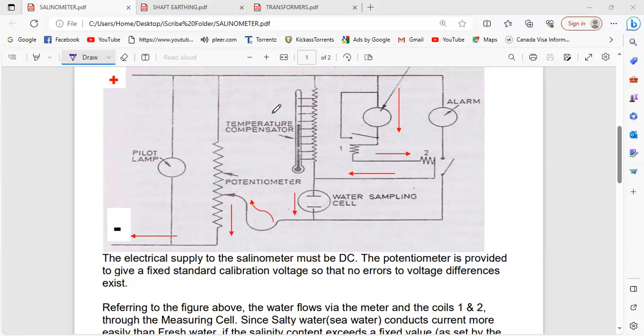So therefore they have a temperature compensator. As the temperature increases, this particular resistance is shorted out, allowing more current to pass through. It is still going to pass through this thing, but it acts as a bypass to this circuit, and this circuit is basically your alarm circuit. So you are avoiding unnecessary alarms.